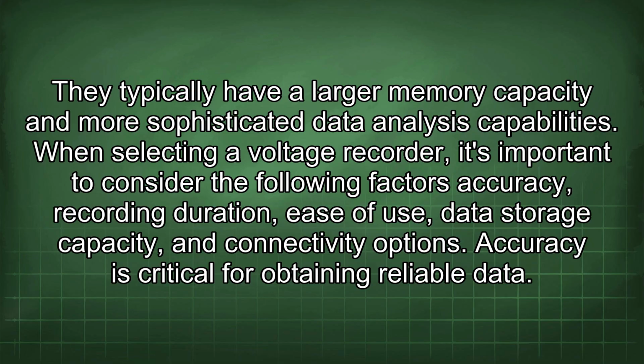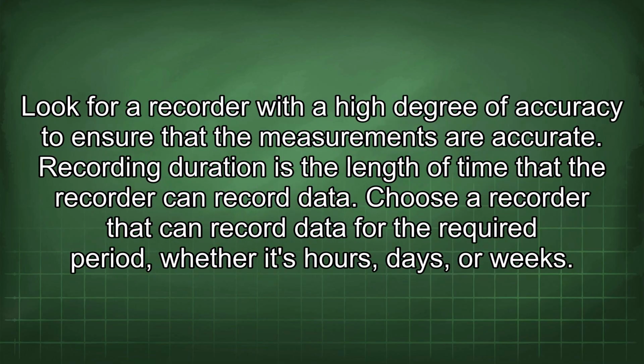When selecting a voltage recorder, it's important to consider the following factors: accuracy, recording duration, ease of use, data storage capacity, and connectivity options. Accuracy is critical for obtaining reliable data. Look for a recorder with a high degree of accuracy to ensure that the measurements are accurate. Recording duration is the length of time that the recorder can record data. Choose a recorder that can record data for the required period, whether it's hours, days, or weeks.